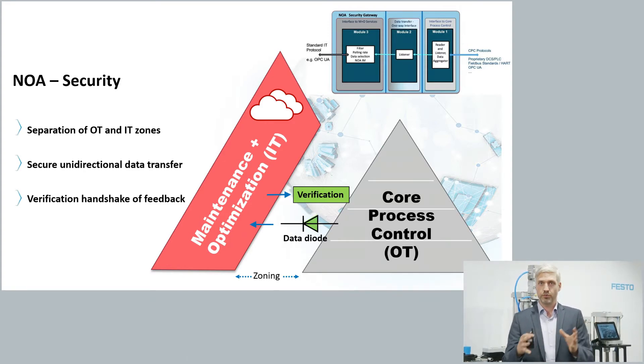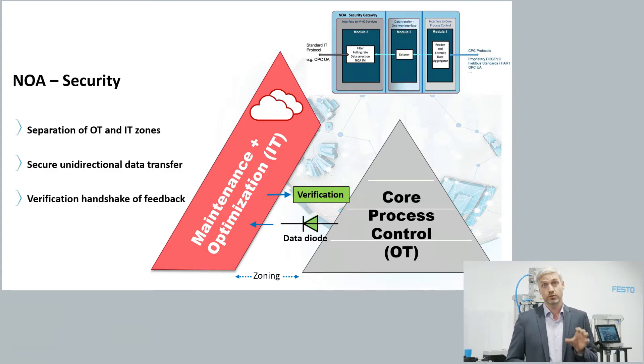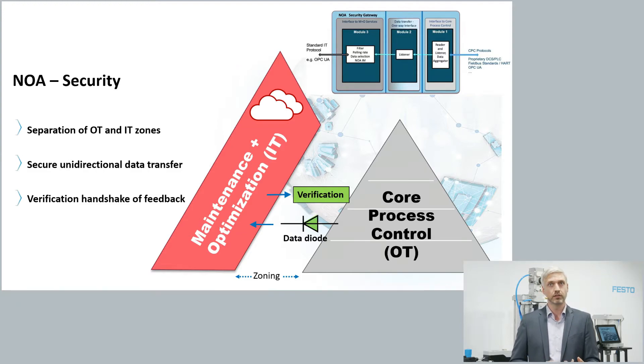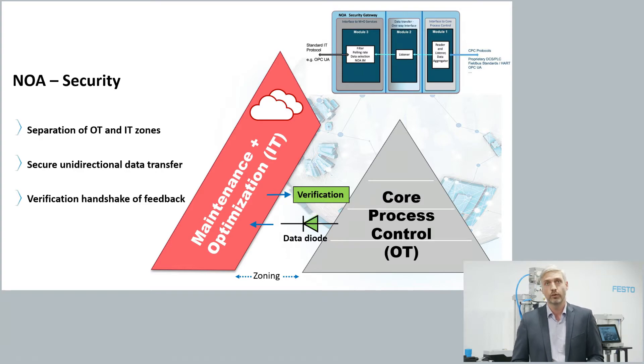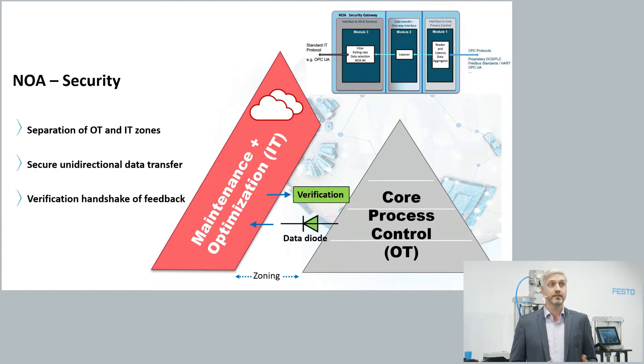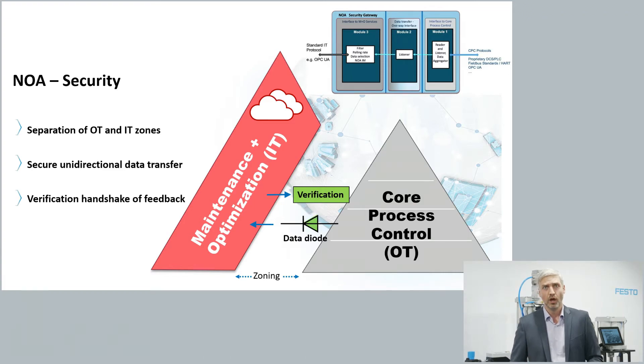An example implementation uses a three-module component: Module 1 has a bidirectional communication interface to core process control, actively pulling required data. Module 2 is not configurable — it simply receives data from Module 1 and passes it to Module 3. Module 3 has a bidirectional communication interface providing NOA information model data via OPC UA to the maintenance and optimization applications. Additional security requirements follow the IEC 62443 standard, and a specific verification process is required when feeding insights from the IT domain back to core process control.